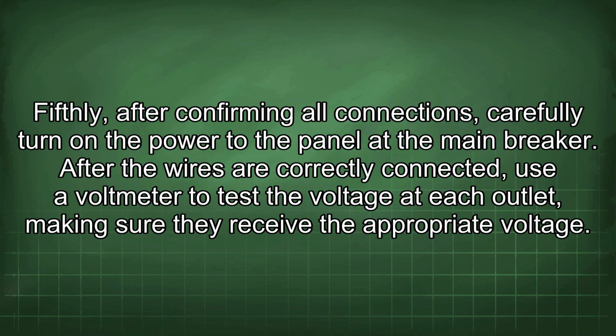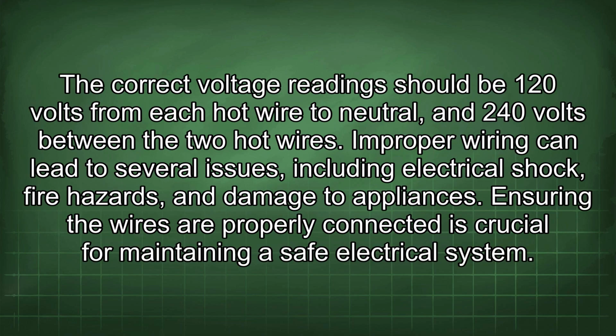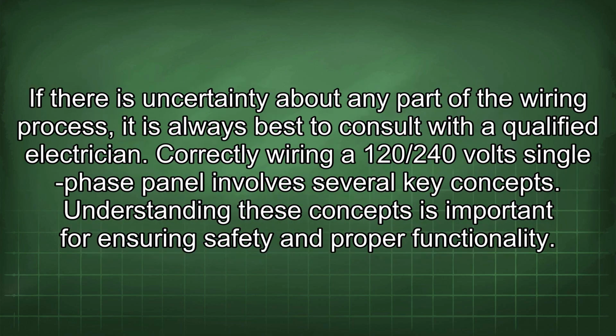After the wires are correctly connected, use a voltmeter to test the voltage at each outlet, making sure they receive the appropriate voltage. The correct voltage readings should be 120 volts from each hot wire to neutral and 240 volts between the two hot wires. Improper wiring can lead to several issues, including electrical shock, fire hazards, and damage to appliances. Ensuring the wires are properly connected is crucial for maintaining a safe electrical system. If there is uncertainty about any part of the wiring process, it is always best to consult with a qualified electrician.